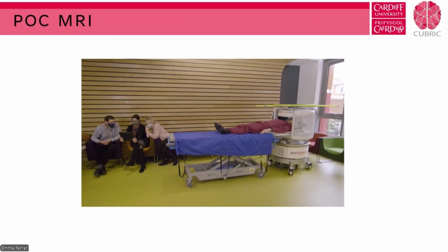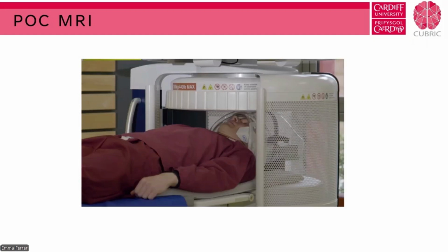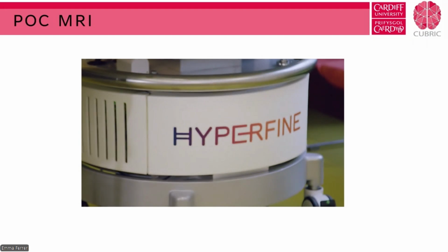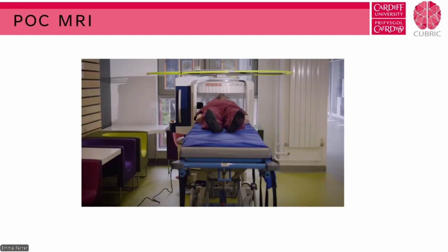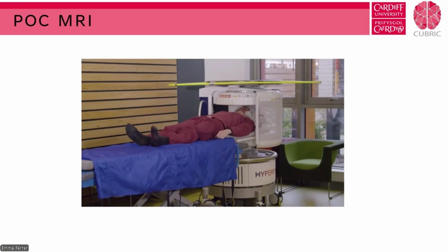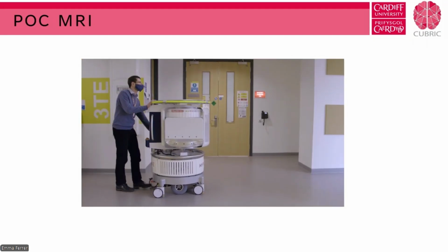The scanner is controlled through a tablet with protocols that are pre-designed. The operator doesn't even need to really position the scan, because there is only a head coil and the position is kind of fixed. So all kind of simple and really fairly portable. The scanner has its own little motor that moves it, and the person who moves it just needs to sort of steer it.